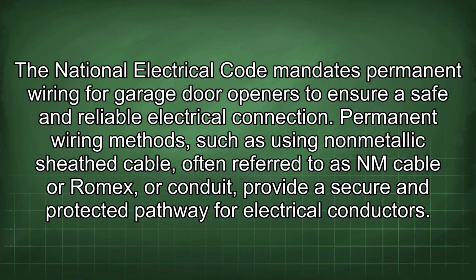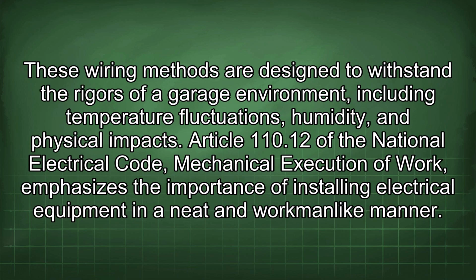The National Electrical Code mandates permanent wiring for garage door openers to ensure a safe and reliable electrical connection. Permanent wiring methods, such as using non-metallic sheathed cable, often referred to as NM cable or Romex, or conduit, provide a secure and protected pathway for electrical conductors. These wiring methods are designed to withstand the rigors of a garage environment, including temperature fluctuations, humidity, and physical impacts.